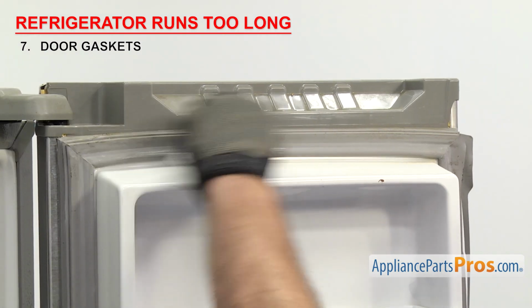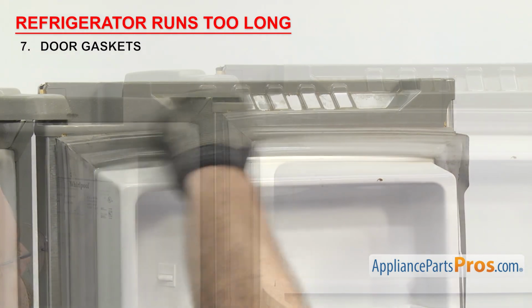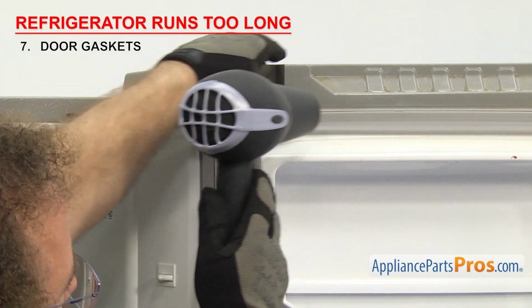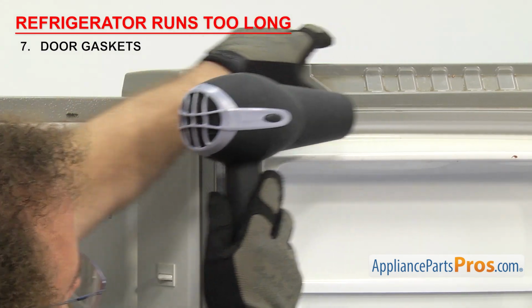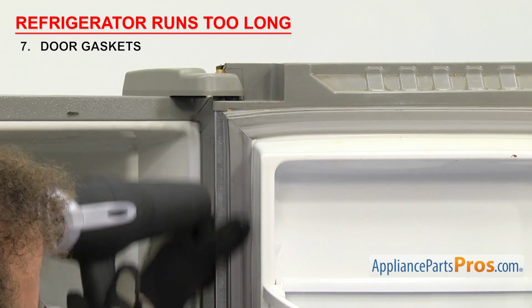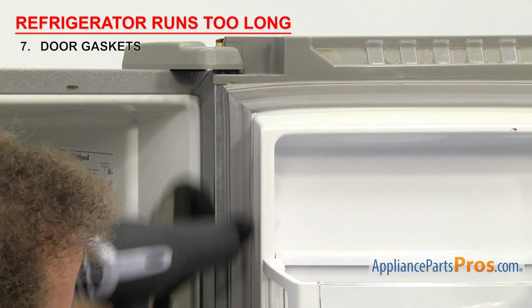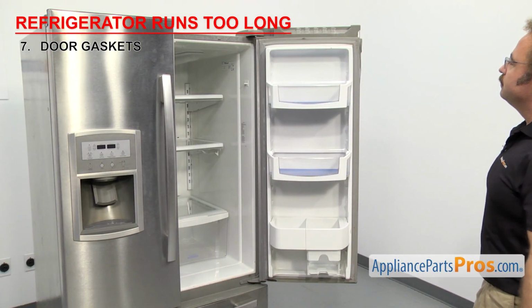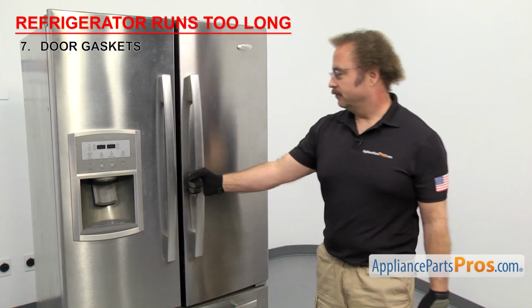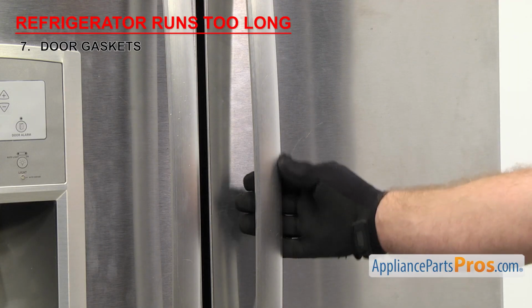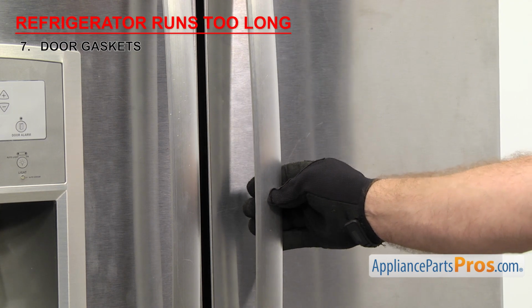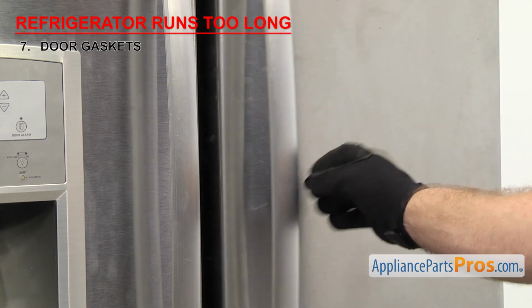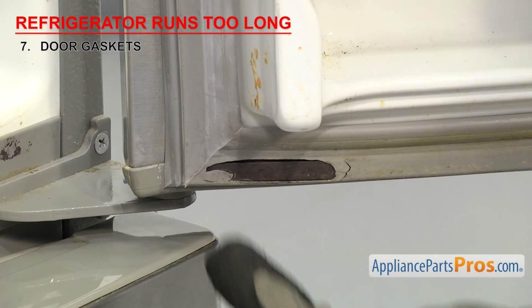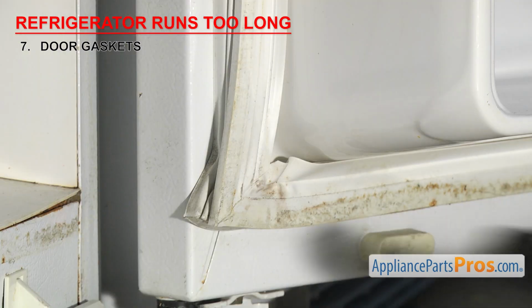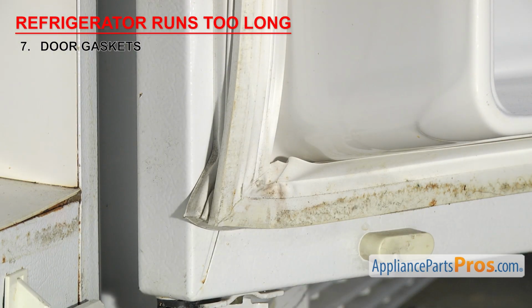Inspect the door gaskets and clean them if needed. Sometimes the gaskets can get deformed, usually on the hinge side, so you might be able to use a hair dryer to heat up the gasket and reform it. It's rare, but sometimes the magnet inside the door gasket can fail and the magnet just won't hold on to the cabinet anymore. You should feel the magnet hold as you start to open the door, and it should hold on to the cabinet when you close the door. If the magnet's failing, the door gasket's damaged, or it's so badly deformed that you can't get it straightened out to allow the door to seal properly, then you'll have to replace it.